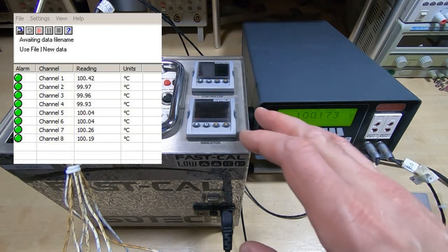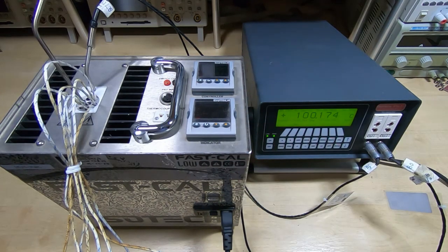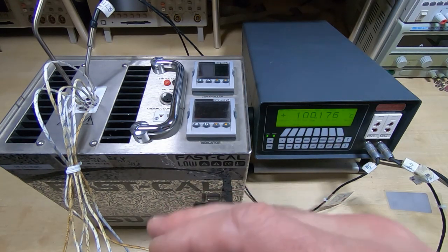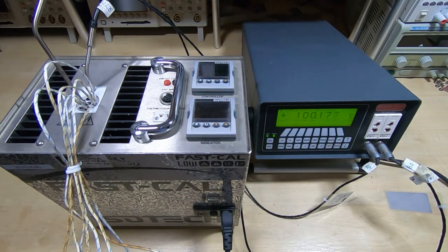So this is what I do. I just go through the entire range I intend to use at discrete steps, check the errors, and then when I get to the end of the run, I will make corrections to the probe and then rerun it to make sure that the corrections have worked.